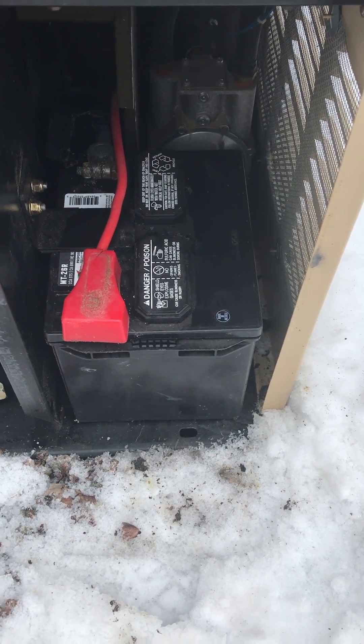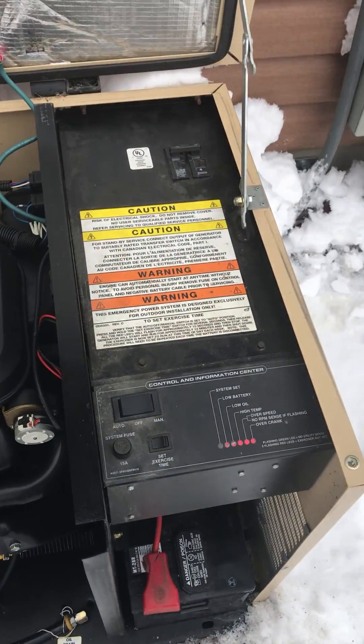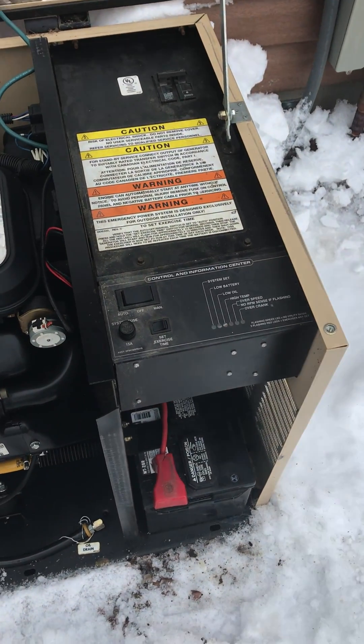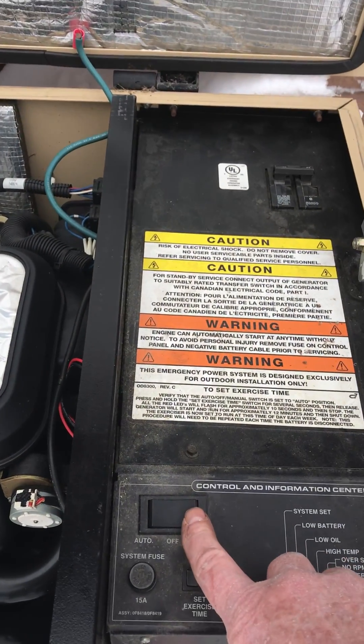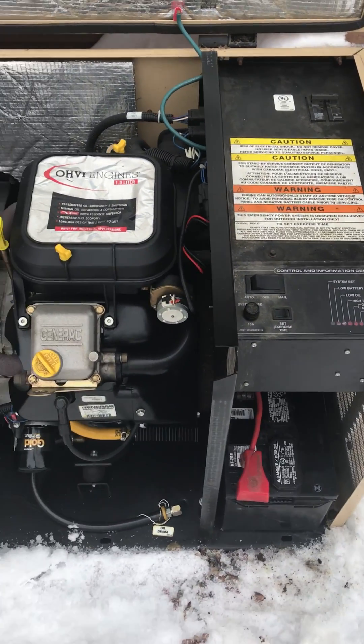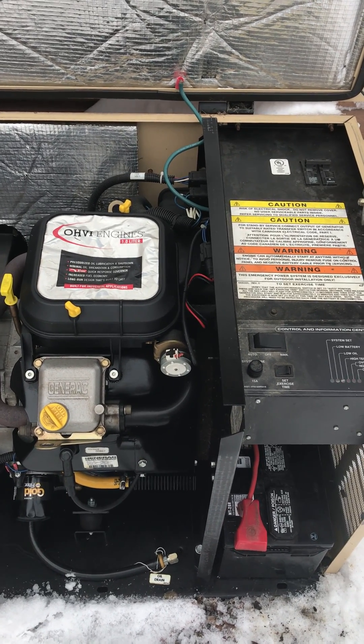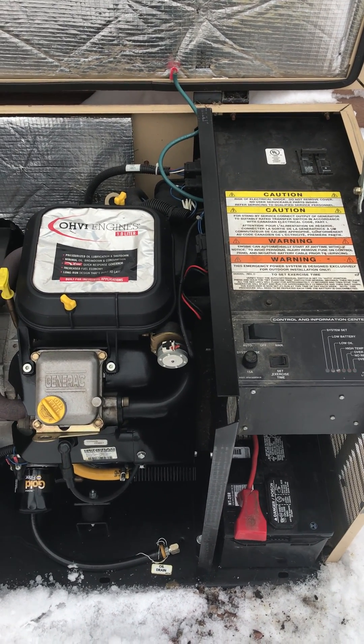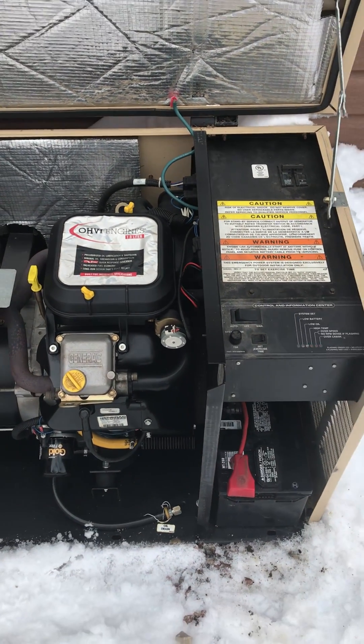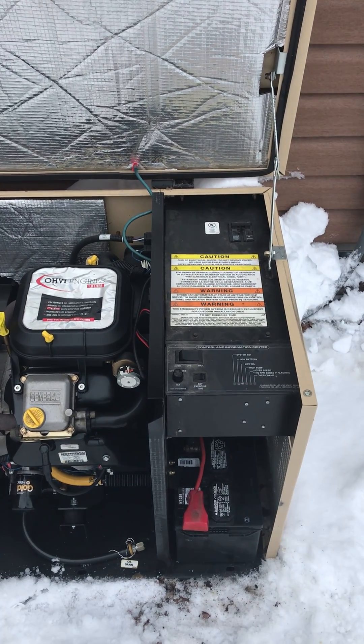So I replaced that piece of junk battery, replaced the fuse, and we'll see whether she starts up or blows the fuse again. Starting it now — there's the first try. It usually does multiple attempts and then faults out on the overcrank.